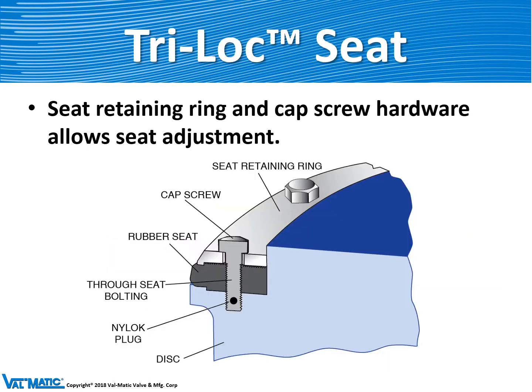Valmatic valves feature the Tri-Loc seating system. In the Tri-Loc system there are three modes that help retain the rubber seat on the disc. The first is the compression of the seat retaining ring. The second are the registers or lips on that ring and as part of the disc. The third is the cap screw bolts which pass through the rubber into the disc to prevent the rubber from blowing out of the disc.